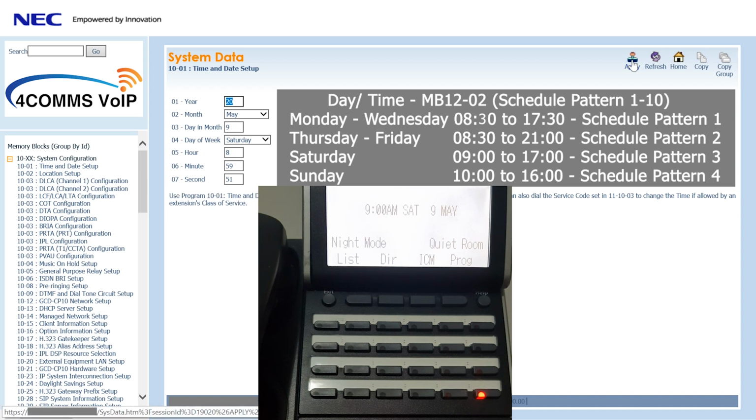One thing to keep in mind, if the fixed operation mode is turned on, which it is right now, you can no longer change the system manually using button 23. It's actually stuck in that mode, or fixed to that mode. Hence the name of the button, fixed operation mode. But once we turn it back off, then we're free to change the mode as we wish. So in this case, the customer will come back on Sunday after the public holiday, turn fixed operation mode off, and then manually put the system into day mode. Then it'll continue on with its timetable and automatically change again.